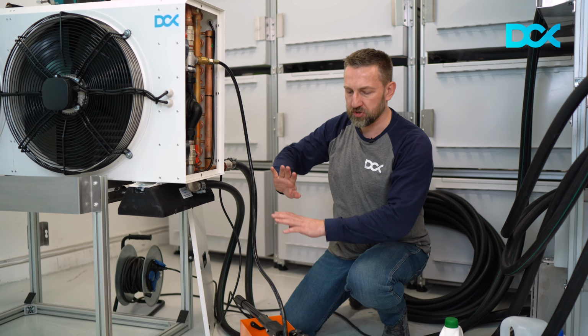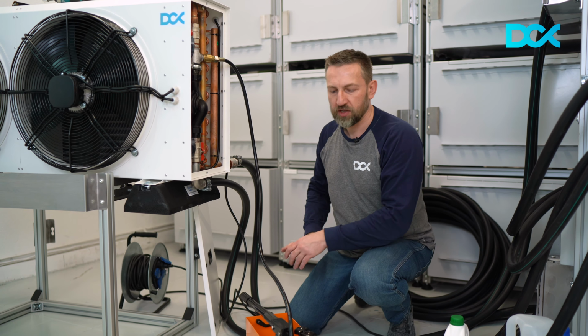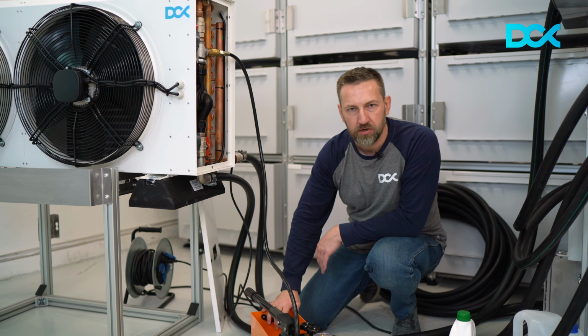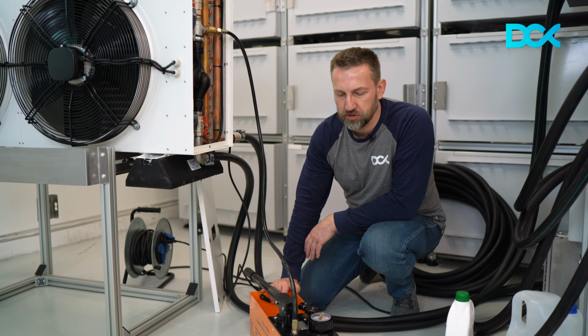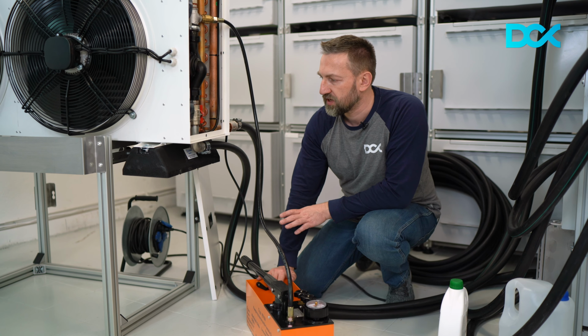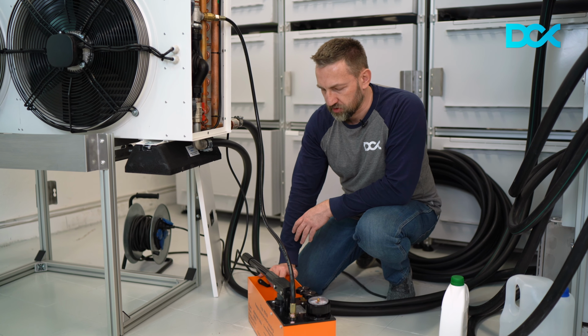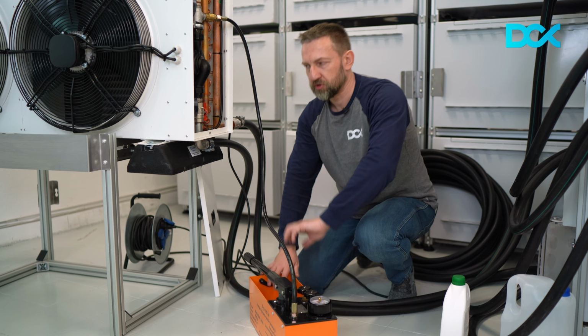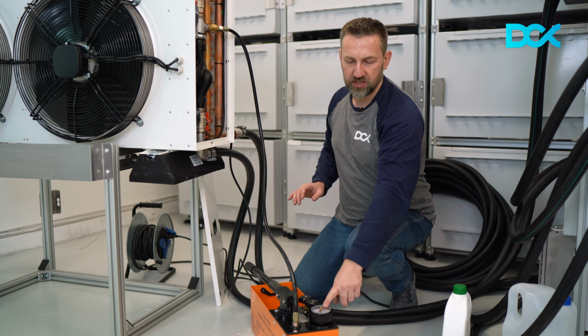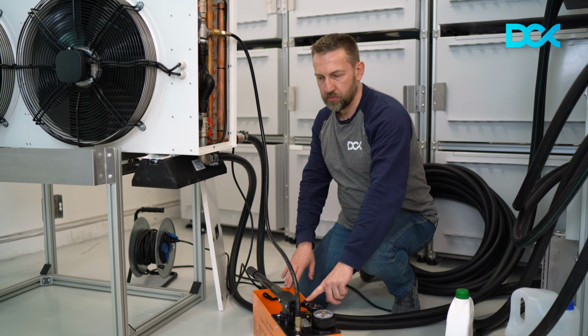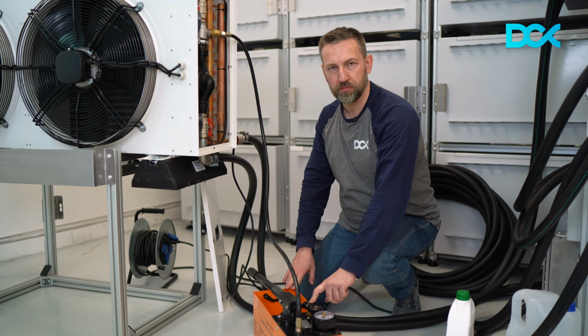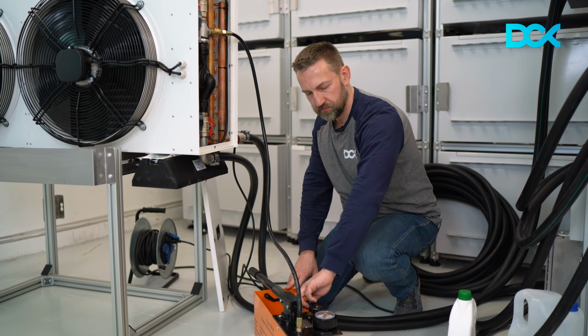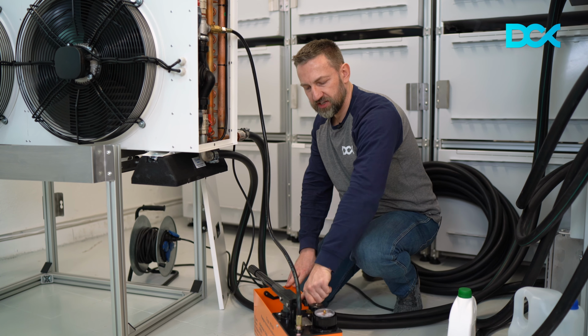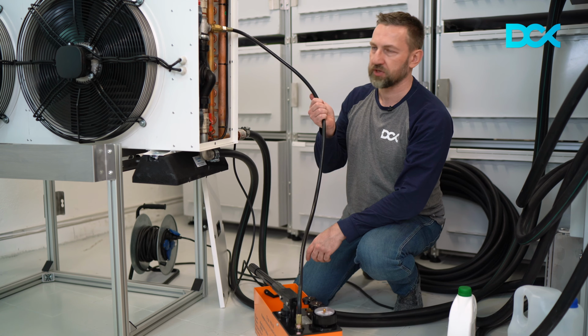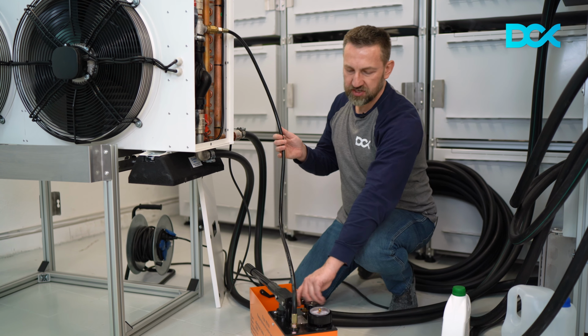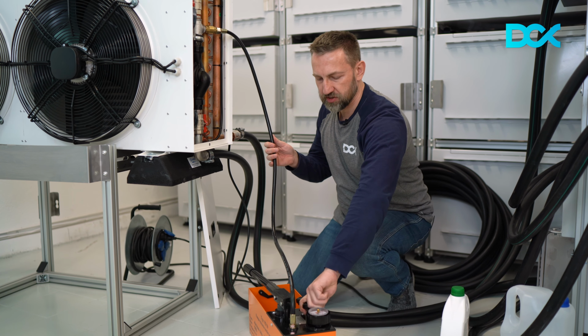So let's assume you filled the whole system altogether. You should observe no more than 1 bar here. It doesn't require putting even more pressure. That's just fine. It will work just fine. After the whole pressurization of the system, when you see 1 bar here, you are basically opening valve number 2, releasing the excess pressure here. You will release all the water from that connection point, and basically that's it. That's everything you need.